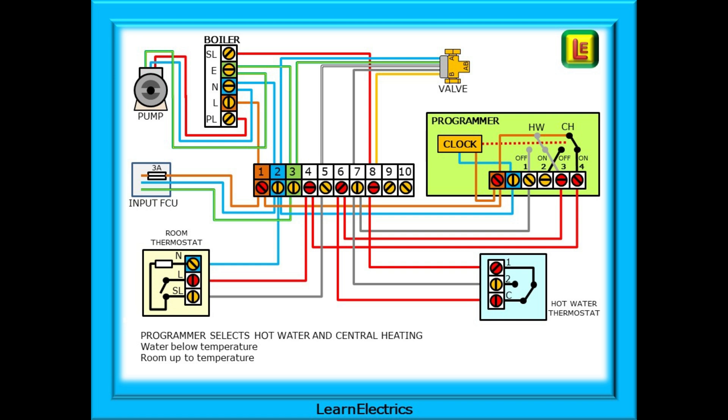Now the programmer selects hot water and central heating. The hot water heating is already enabled as the water thermostat is connecting C and one. So what happens to the central heating? With the room up to temperature and the thermostat in the open position, 240 volts flows from programmer number four terminal to wiring center terminal number four, and then down to the L terminal on the room thermostat, where it stops. The central heating is not enabled.